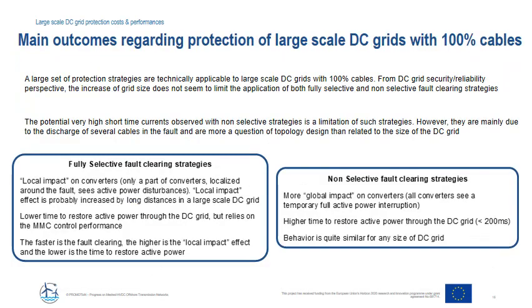The two following slides give some main outcomes regarding the protection of large-scale DC grid with 100% cables. A large set of protection strategies are technically applicable to large-scale DC grid with 100% cables. From a DC grid security reliability perspective, the increase of grid size does not seem to limit the application of both fully selective and non-selective fault clearing strategies. The potential very high short-time currents observed with non-selective strategies is a limitation of such strategies. However, they are mainly due to the discharge of several cables in the fault and are more a question of topology design than related to the size of the DC grid.